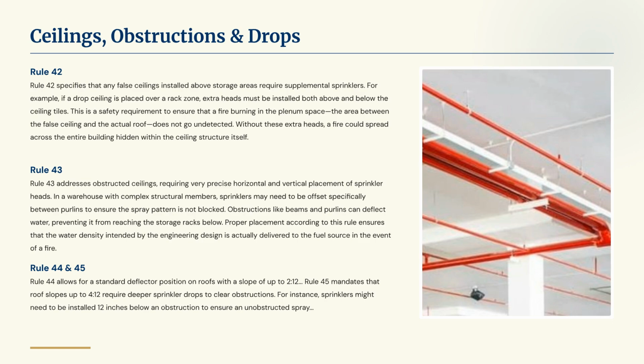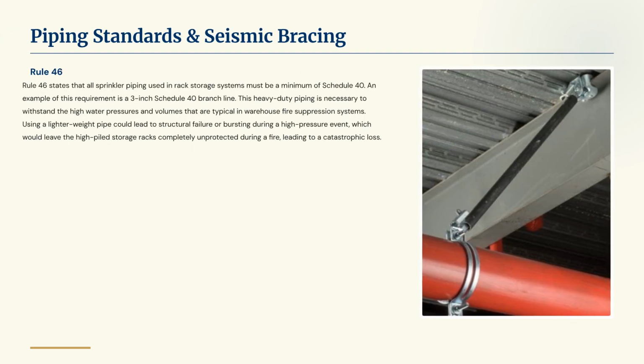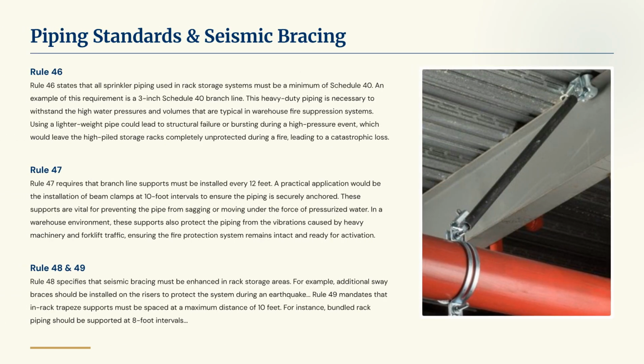Rule 43 addresses obstructed ceilings, requiring precise placement of sprinkler heads. Rules 44 and 45 relate to deflector position and required sprinkler drops based on roof slope. Rule 46 requires all rack storage piping to be a minimum of Schedule 40. Rule 47 mandates branch line supports every 12 feet.